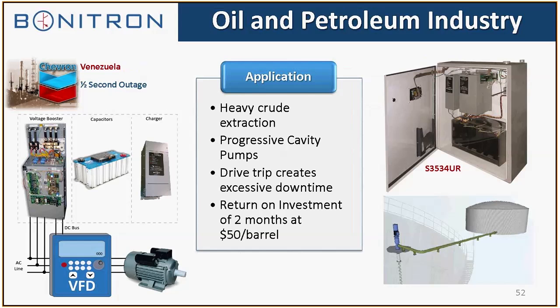And going back to the application I mentioned earlier, this is the PCP pumps. We're seeing a lot of U.S. companies getting involved in pumping applications globally. I've specified probably 3 or 4 of these, and it's usually right around a half a second, and it's always ultracapacitors. And the return on investment is dependent on the price of oil. And I know it's fairly low, but when it was at $50 a barrel, it was a 2-month return on investment. And everything went in one cabinet. It was a half a second, 60 horsepower application, and that shows you a picture of the actual PCP pump and the coiled pumping line that goes down into the ground. That's the big concern when it trips on undervoltage.